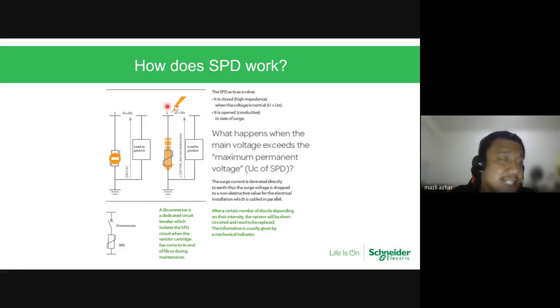Then the excess voltage that flows will not go to the equipment, it will go directly to the earth. So your equipment is safe, and then it will ensure that the network is still protected. And then SPD is a self-sacrifice device, which means after a few big strikes, it will start to kaput, tak boleh pakai dah, then you need to change to a new one. So every SPD, we have an indicator at the front. Normally white is operating, white or green, and then red, you need to change.